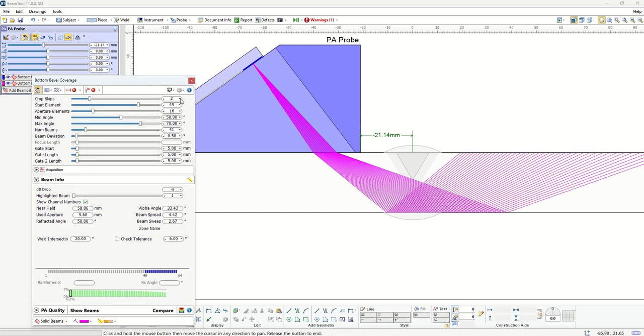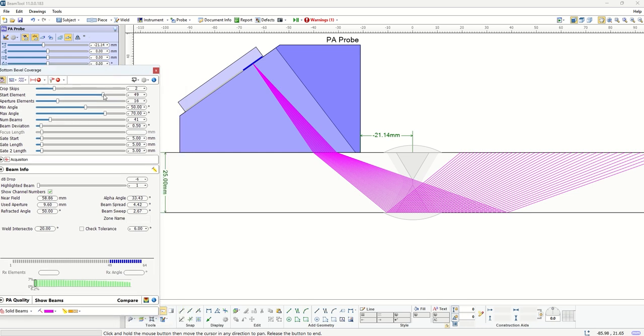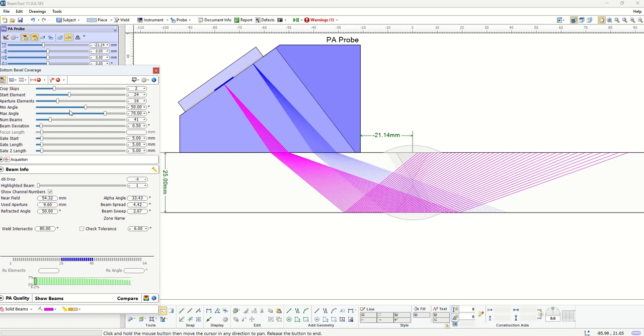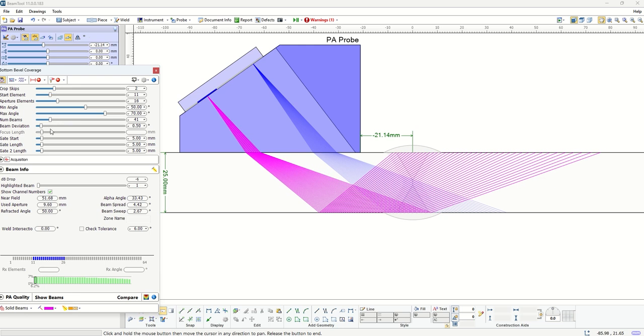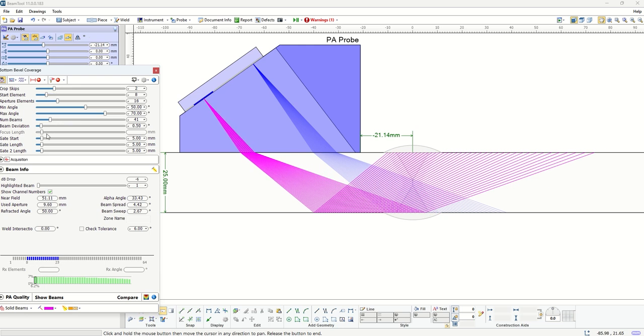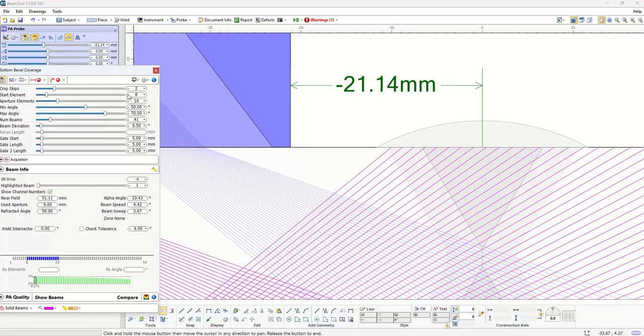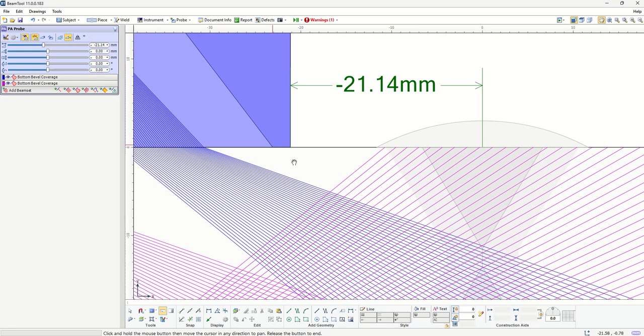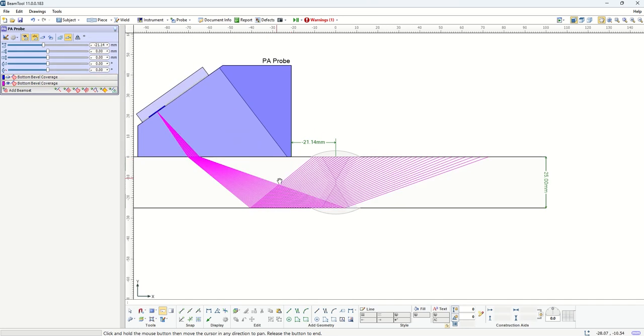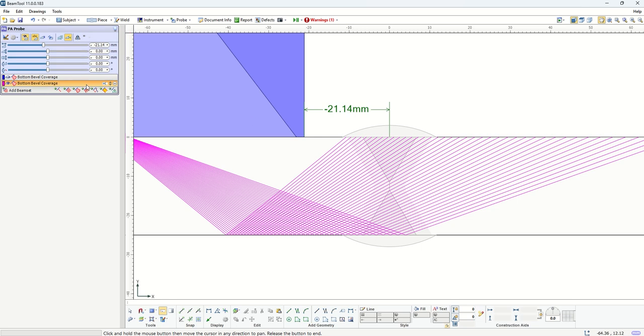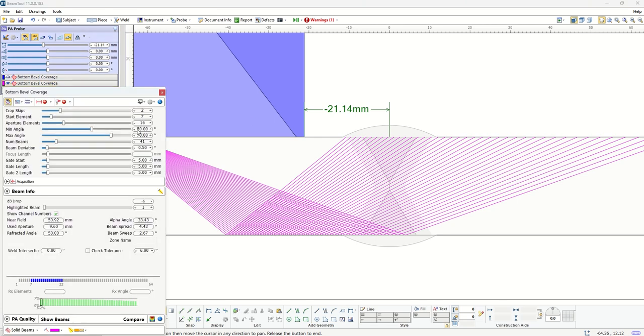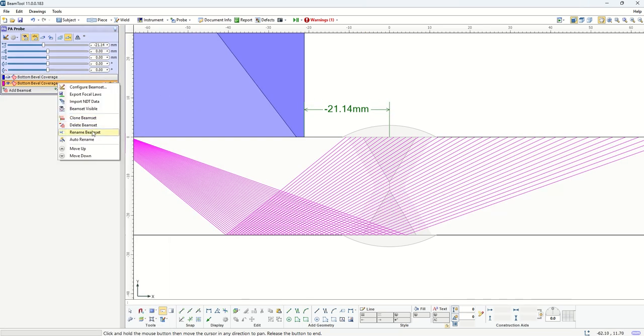And then I will go back to use apertures toward the beginning, toward the lower apertures of the probe. And you notice that as I do that, after the skip, I can easily cover the top bevel. Maybe I can go slightly lower to a start element of 7. If I for a second just turn off the previous one, you will see that with my angles still between 50 and 70, by choosing the smaller part of the aperture, I can now cover the top bevel. And now I'll rename this to top bevel coverage.